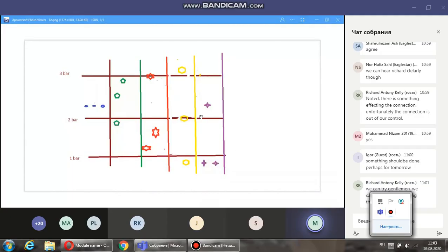Main lube oil pressure is 2.6, this is 2.3. So let me put it in a different way. Out of the three, which one do you think is the bad sensor? These two are showing 0.8 bar. This is 2.3 bar. From there you can pick. The 2.3 bar, sir, that one is correct, because your engine oil pressure is 2.6 bar. So these two sensors are faulty. Yeah, so these two are faulty.